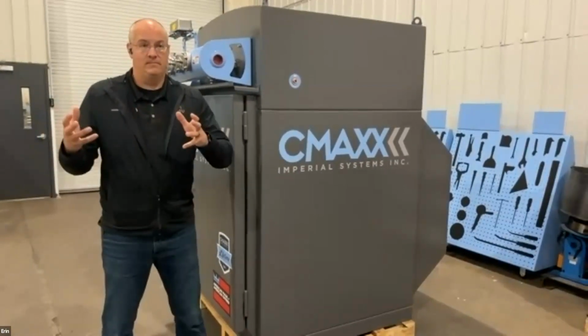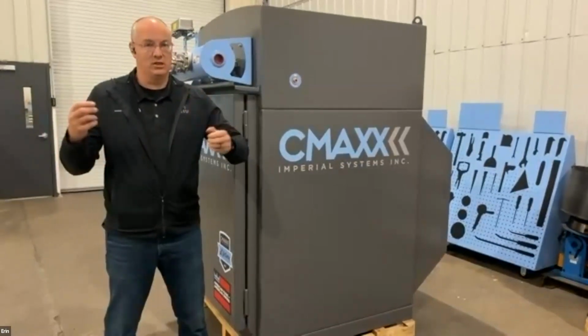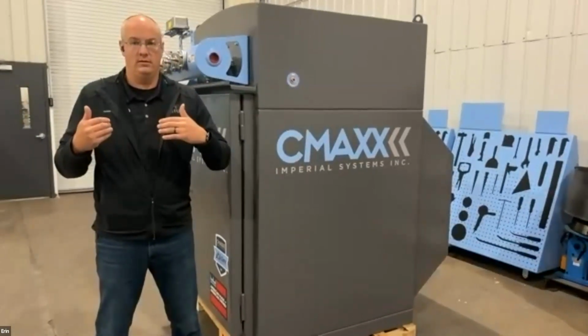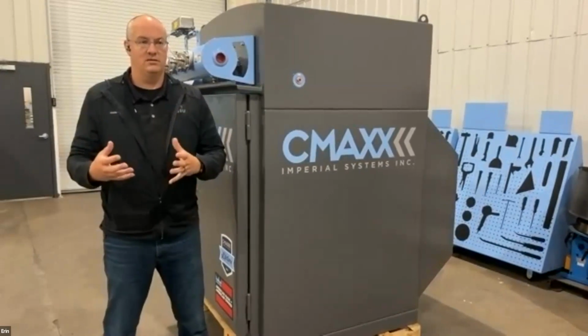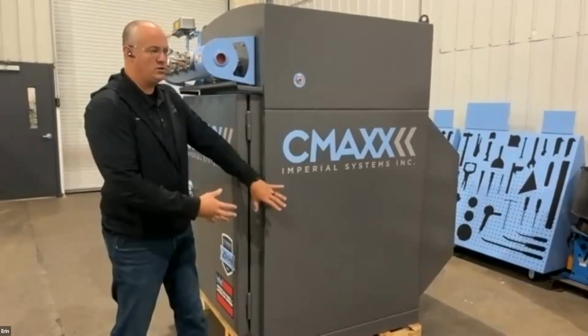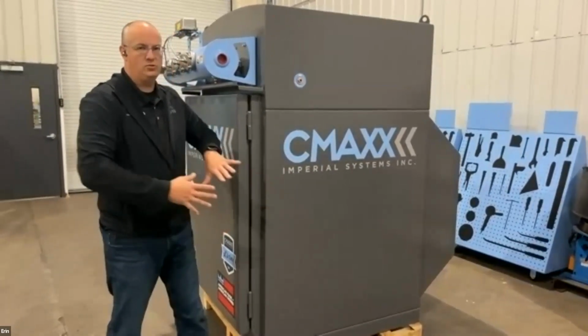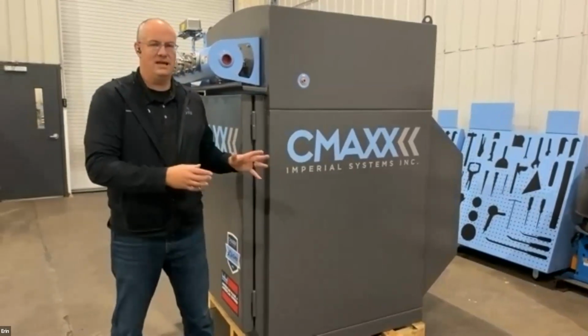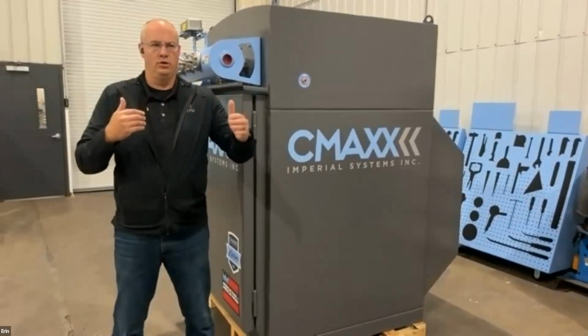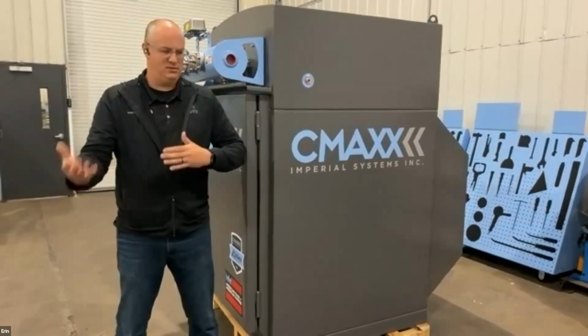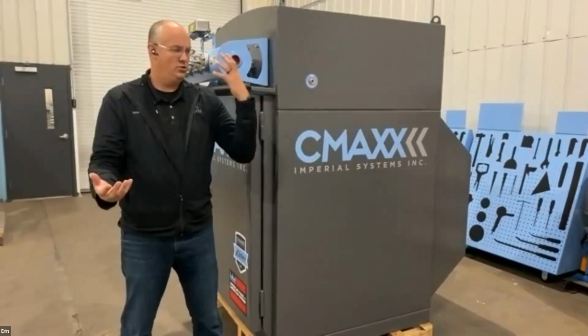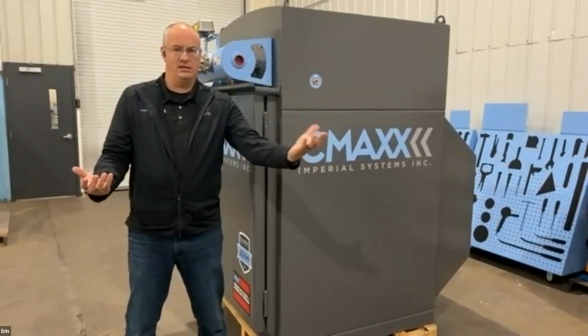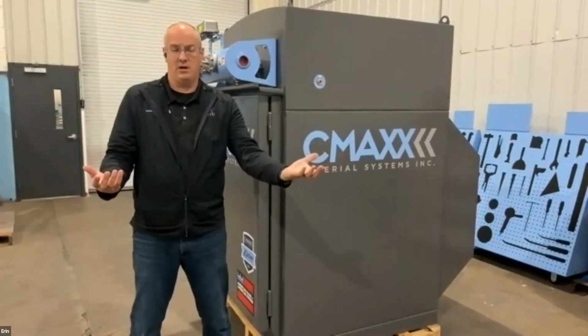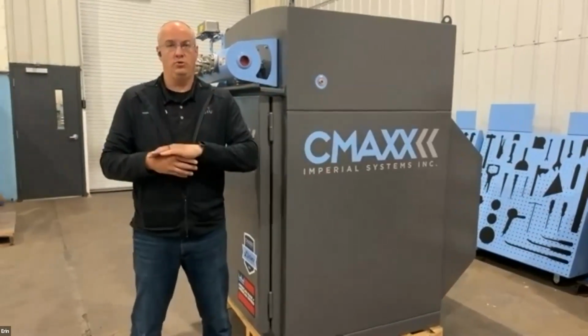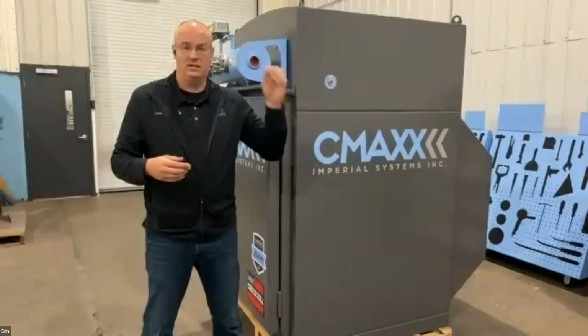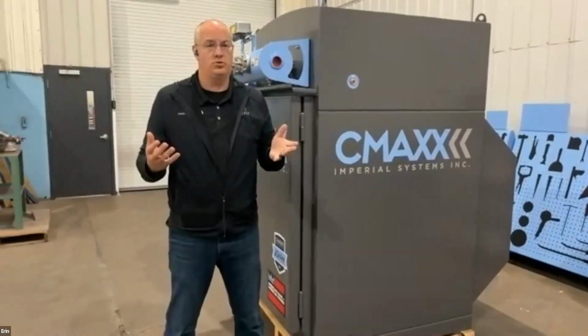With that, you're still kind of taking a little bit of a chance on what is actually going to be safe, because when you get a brand new collector, it's been tested. We know all the ratings. We've done that. And so when it goes out in the field new, you can have your dust test. You know how explosive the dust is. You can then make sure that you have a collector that is protected properly and sized properly when you start from scratch. When you get into older facilities, it gets tricky.